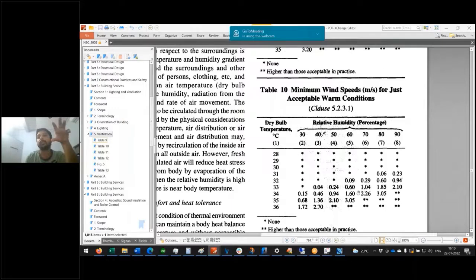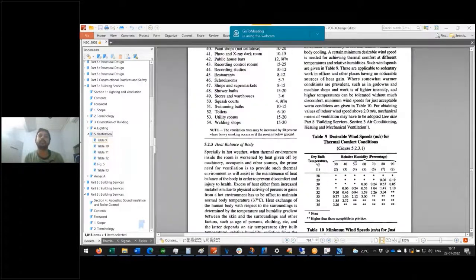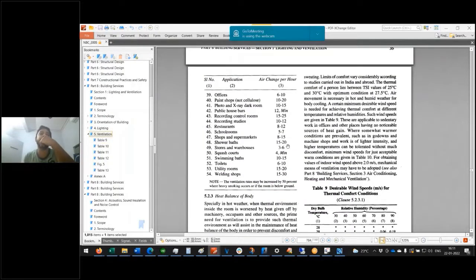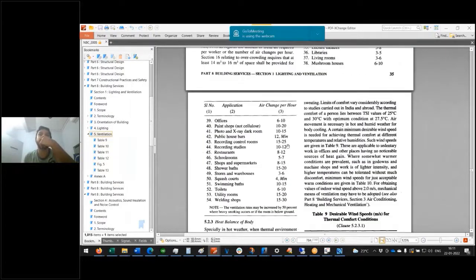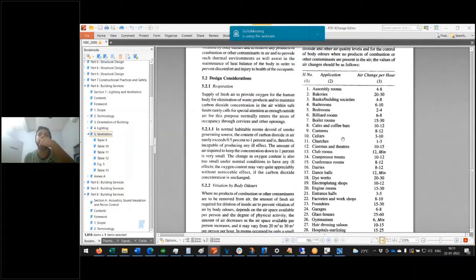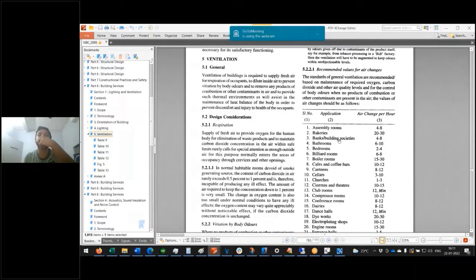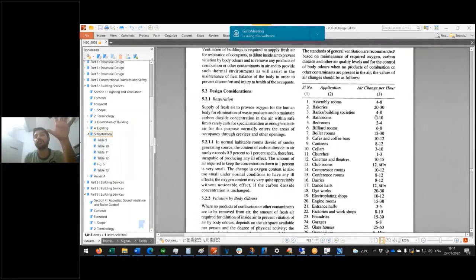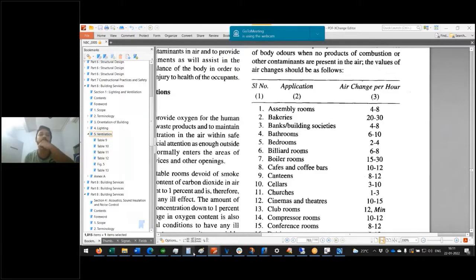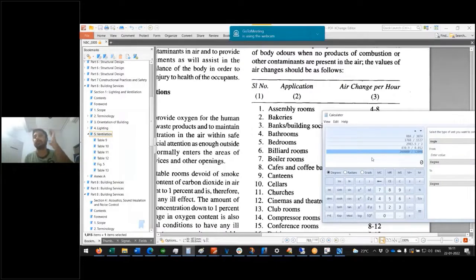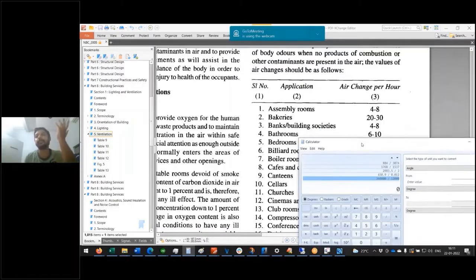But you still need to fulfill this condition. Air changes per hour also needs to be fulfilled, because you have to maintain the oxygen also. So you have the entire volume of air. Let's say I want air changes per hour. Let's say my room is 10 meters by 10 meters, and height 10 meters.